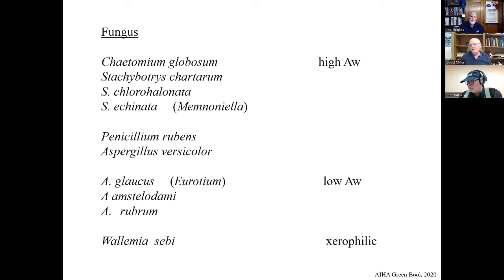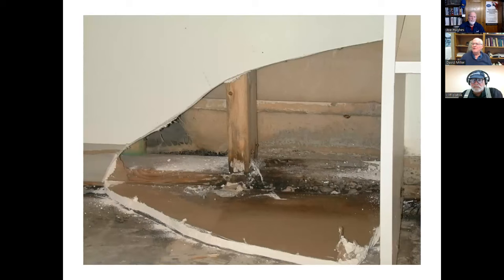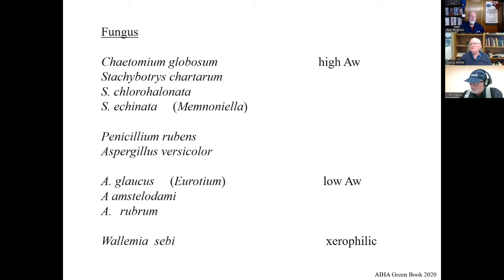And then the last thing, which I mentioned to Cliff just as we were starting, is that it turns out that these fungi, well, they've been working away in that envelope for about 4 or 5 years before it really became obvious to the occupants that there was a problem, that as the fungus grows a little bit, it makes chemicals that are hygroscopic. So think about sugar or salt you leave out in a humid area, it absorbs moisture like a desiccant, and fungi can do that too. So again, you can get circumstances where you would get really slow growth. You think the humidity or the moisture was okay, but the fungus is able to capture more. And most of these things aren't necessarily very common as problems, but they do arise. So it was just a first thought about moisture.